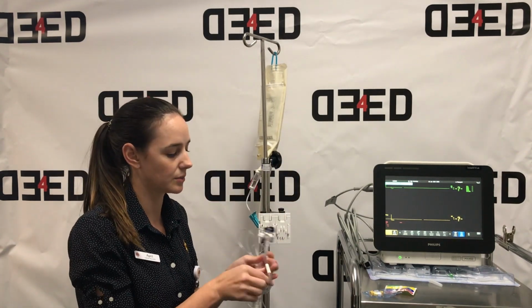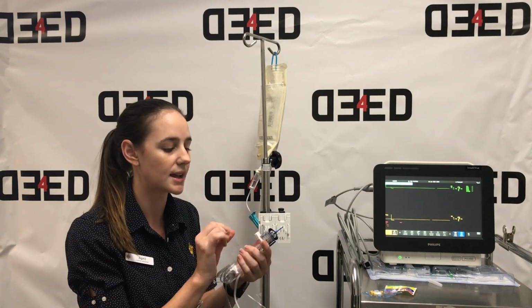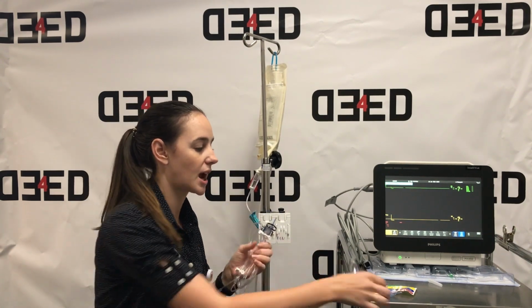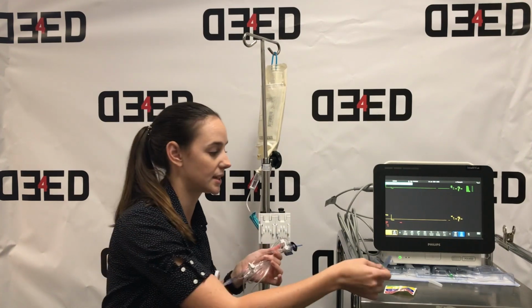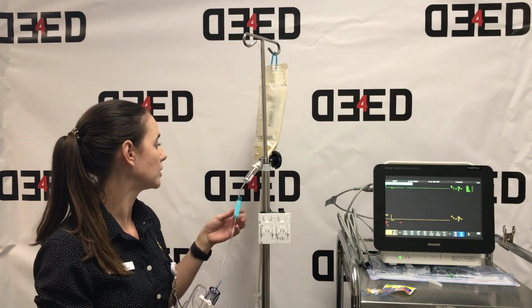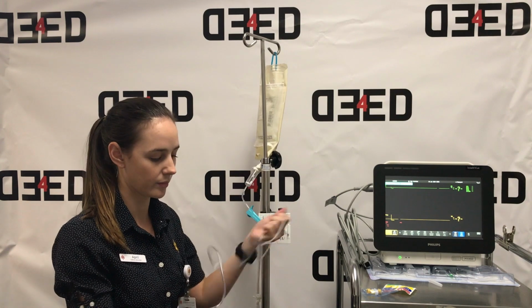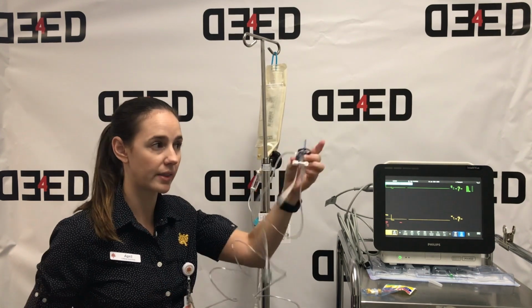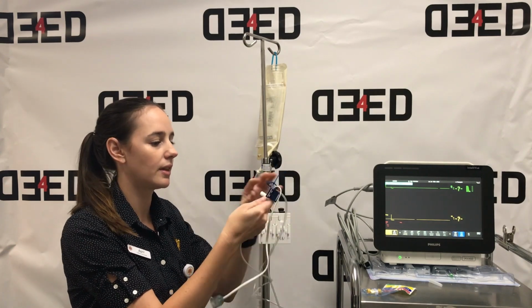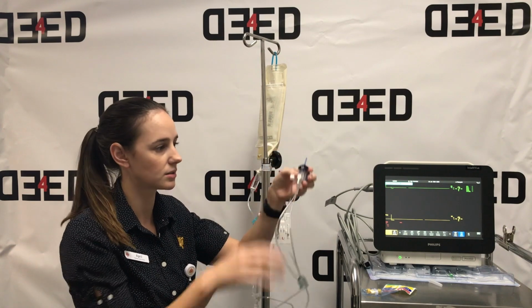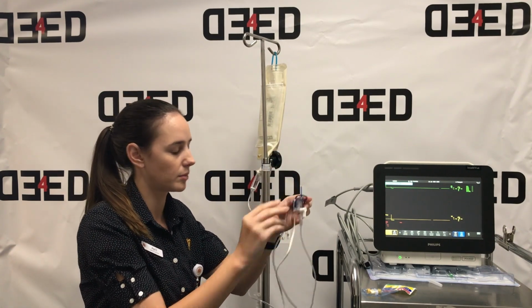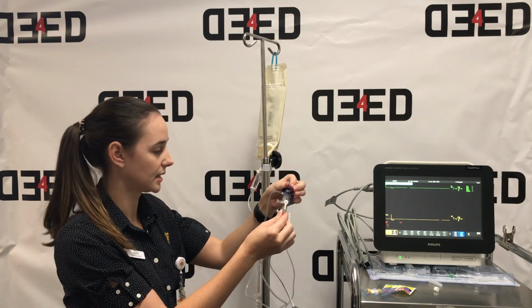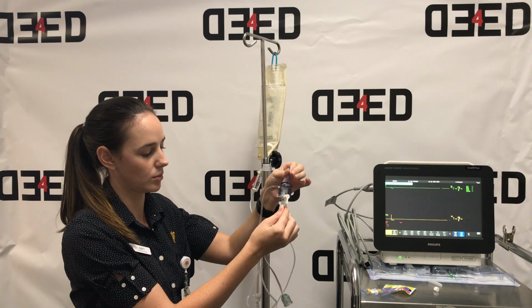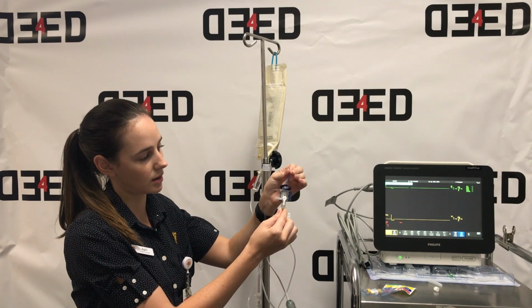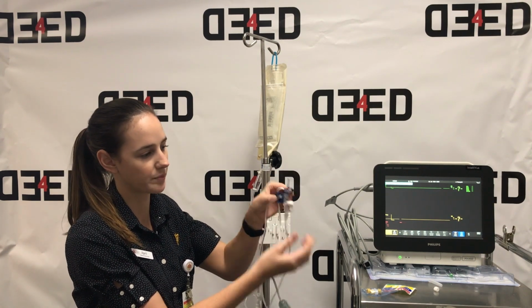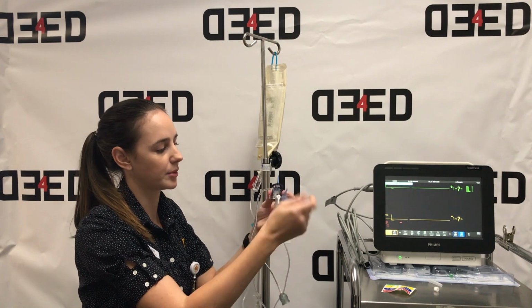One thing you'll notice is that when you get the line out, there's white vented caps on all the ports. So these need to be changed to the non-vented caps, and that way you know you also primed each of the ports as well. So what you can do is open up that roller clamp, come down to the first port where the IV mounting system is, and then turn the connection off to the patient. Open up this port there and give this a little bit of a tug, and what you can see is, in real life you'd see the water, the saline, coming through the line. Wait until that's fully primed and the water comes out that port. Then you can pop your non-vented cap on.